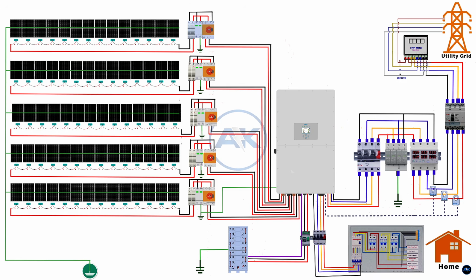Verify that all DC connections are tight and correctly polarized. Confirm that all DC fuses are installed and rated correctly. Make sure the DC isolator is in the off position. Check the battery connections again. Confirm correct polarity, secure terminals, communication cable connection, and battery breaker in the off position.